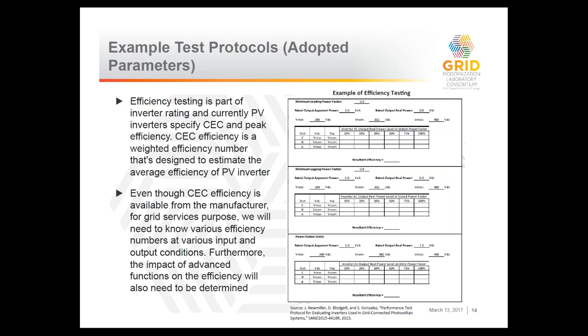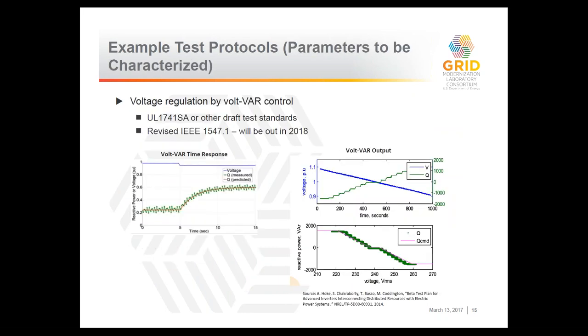But the disclaimer here again is that even though the CEC efficiency is available from the manufacturer, for grid service purposes we need to know the efficiency at various input and output conditions. Furthermore, the impact of the advanced functions on efficiency will also need to be determined. When you have all those additional functions on top of the basic operation of the inverter, how are they going to impact it? And my last slide shows an example of test protocols where parameters are to be characterized.